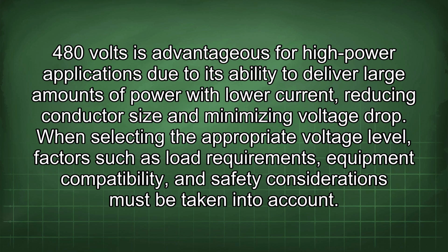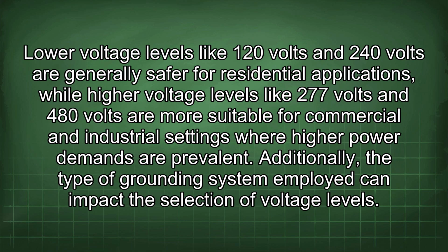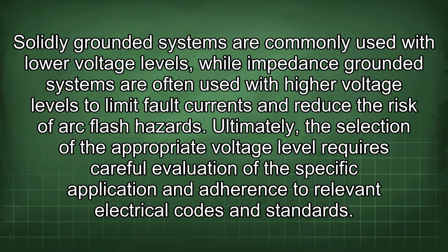When selecting the appropriate voltage level, factors such as load requirements, equipment compatibility, and safety considerations must be taken into account. Lower voltage levels like 120 volts and 240 volts are generally safer for residential applications, while higher voltage levels like 277 volts and 480 volts are more suitable for commercial and industrial settings where higher power demands are prevalent. Additionally, the type of grounding system employed can impact the selection of voltage levels. Solidly grounded systems are commonly used with lower voltage levels, while impedance grounded systems are often used with higher voltage levels to limit fault currents and reduce the risk of arc flash hazards.